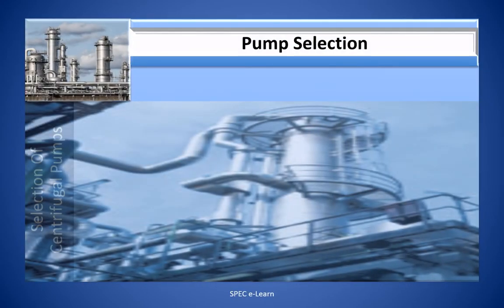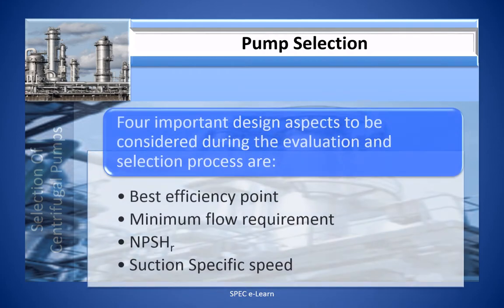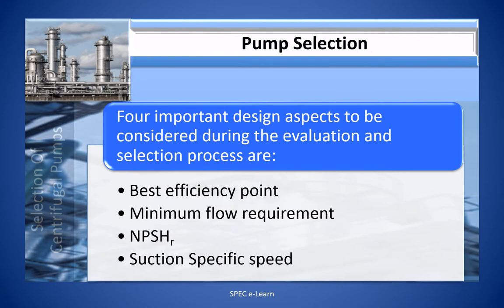Having understood what technical data are required for evaluating the pump, let us now turn our attention to the key parameters that are important from the performance and stability viewpoint. The four important design aspects to be considered are best efficiency point, minimum flow requirement, net positive suction head required, and suction specific speed.